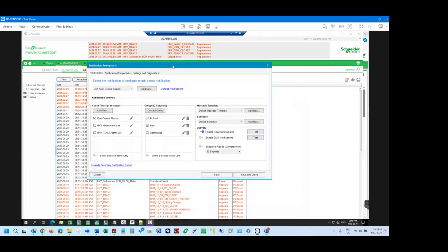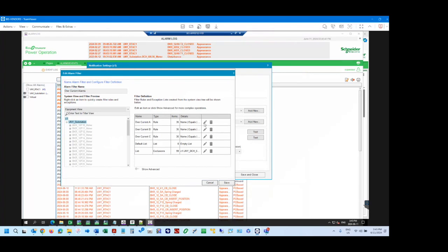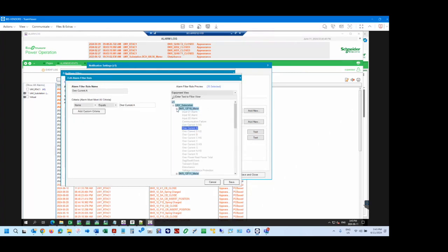And looking at your example there, it looks like you can actually configure any type of alarm you want to, realistically. There wasn't anything specific to tags that exist. Yeah, these are all alarms, and a lot of these are disturbance, sags, swells. These are all those onboard alarms that I'm talking about, coming from the ION meter.